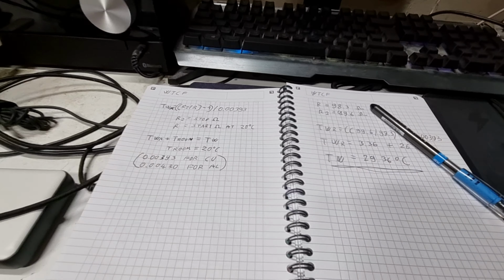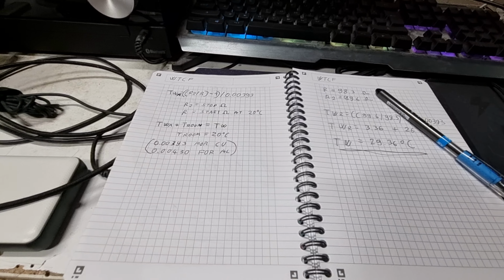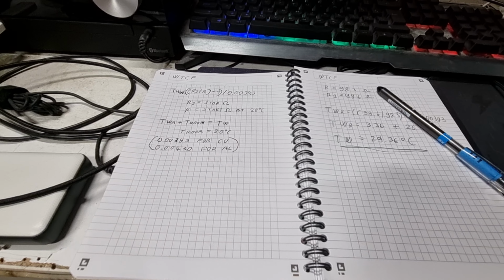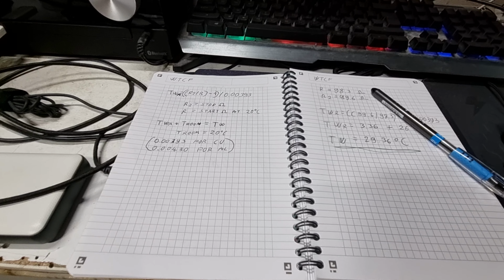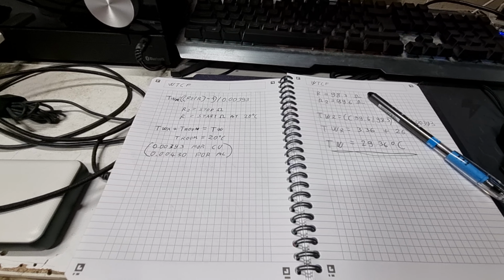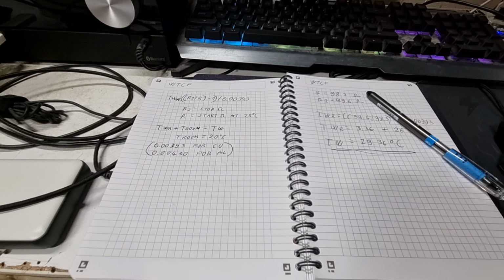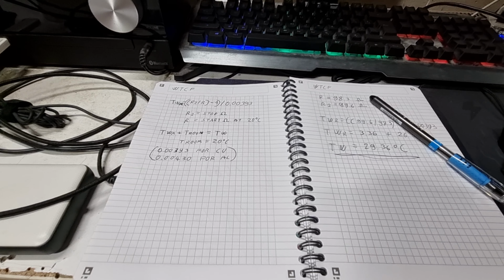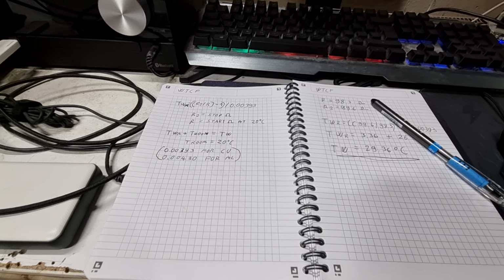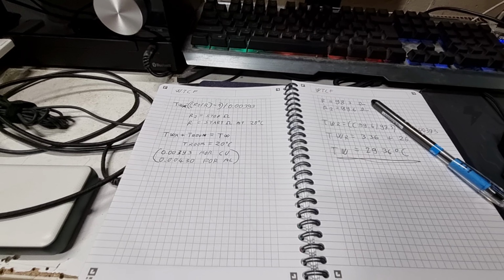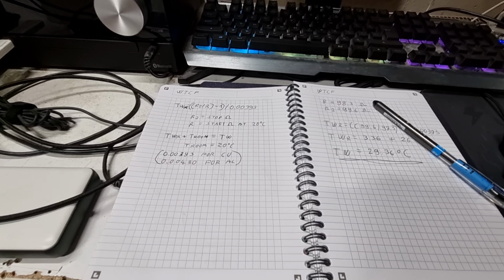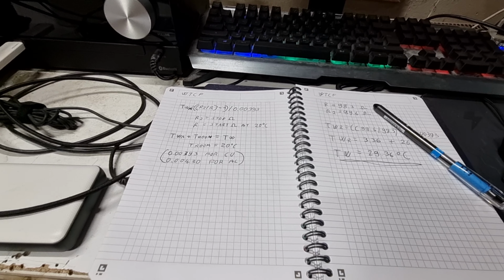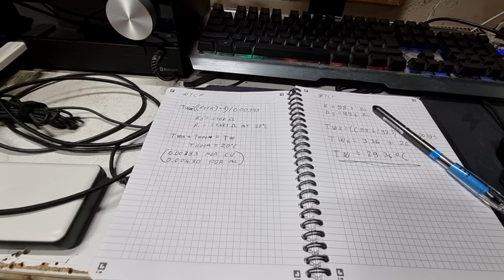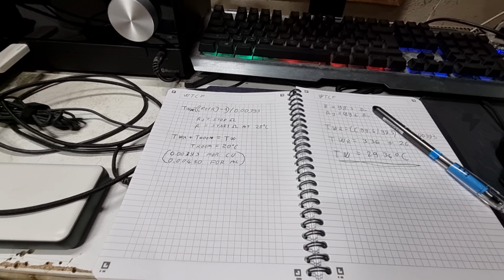It's a very small increase because we only ran it for about 2 minutes, and again it was very ballasted, with active power of only about 500 watts. The reactive power was much greater, around 15 to 16 amps. If it were unballasted and we drew something like 35 amps from the mains, the winding temperature would increase quickly.